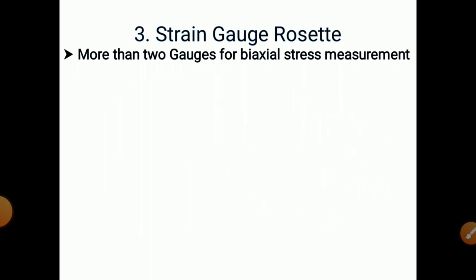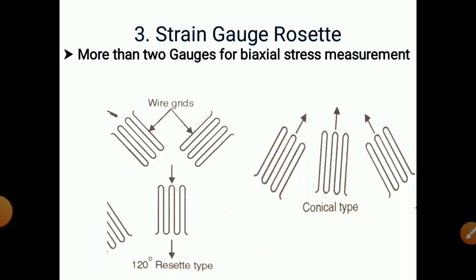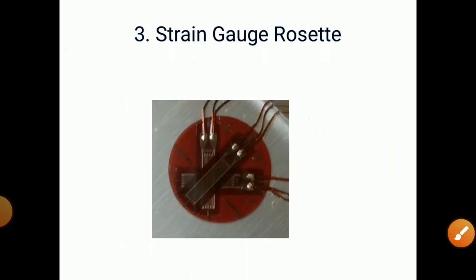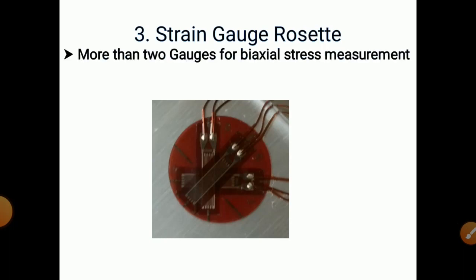The third type is the strain gauge rosette. More than two gauges are used for biaxial stress measurement. If we want to measure biaxial stresses, we use two or more strain gauges. Here a 120-degree rosette type is shown where three strain gauges are used at 120-degree angles. You can also use conical type strain gauges for measurement of biaxial stresses.